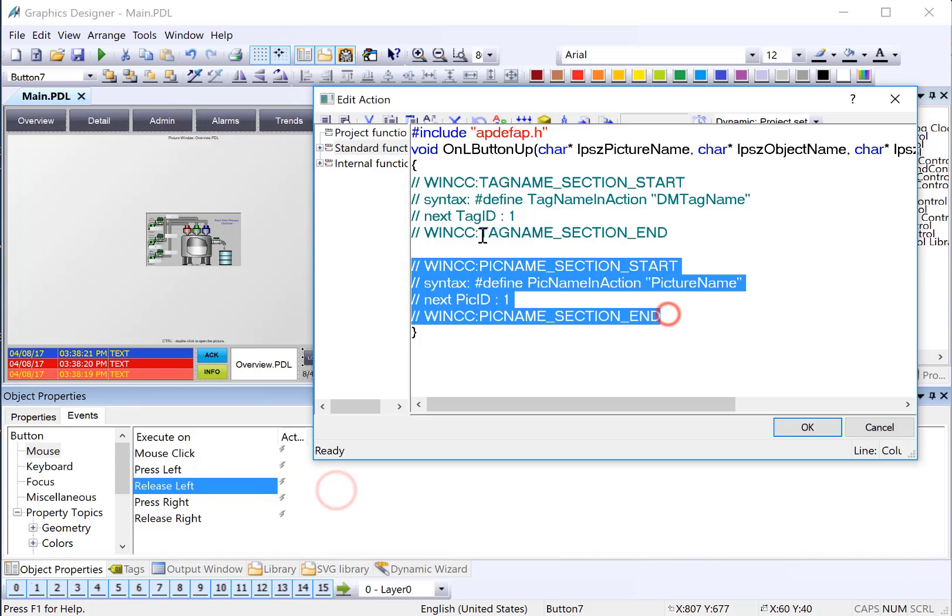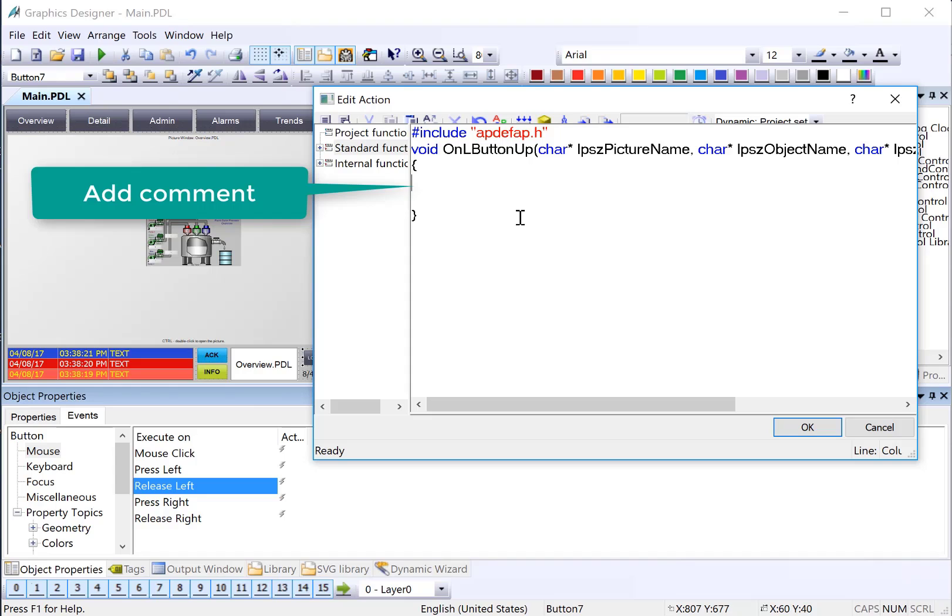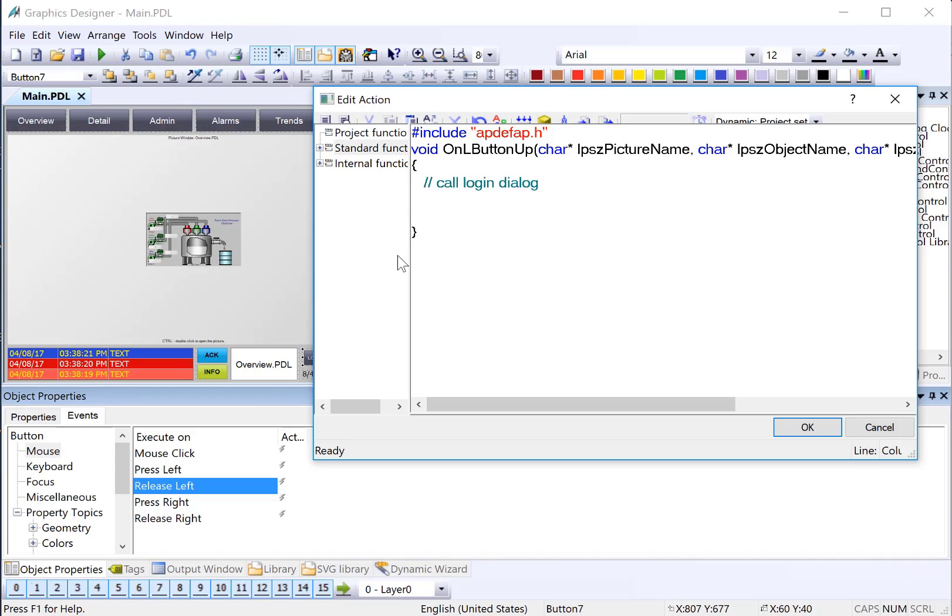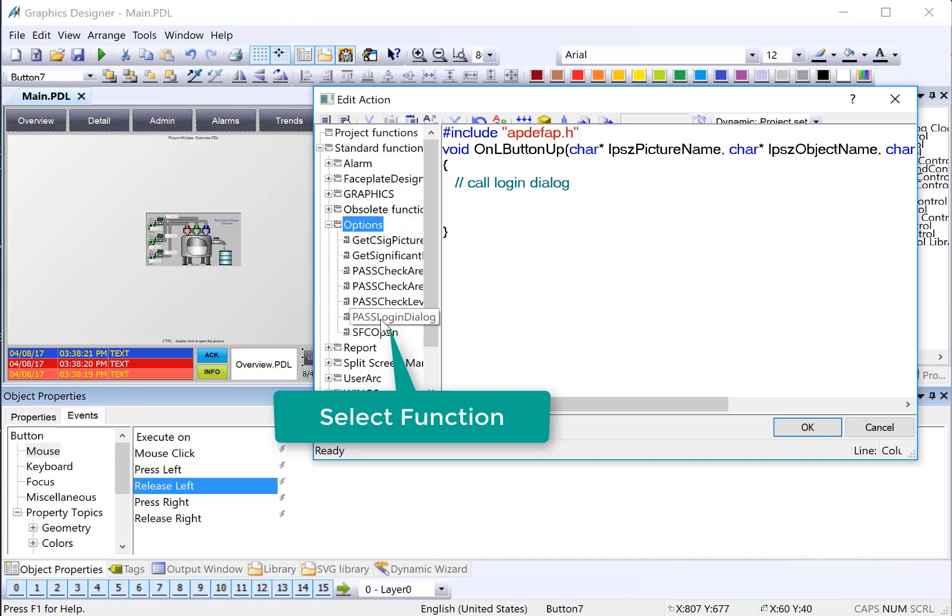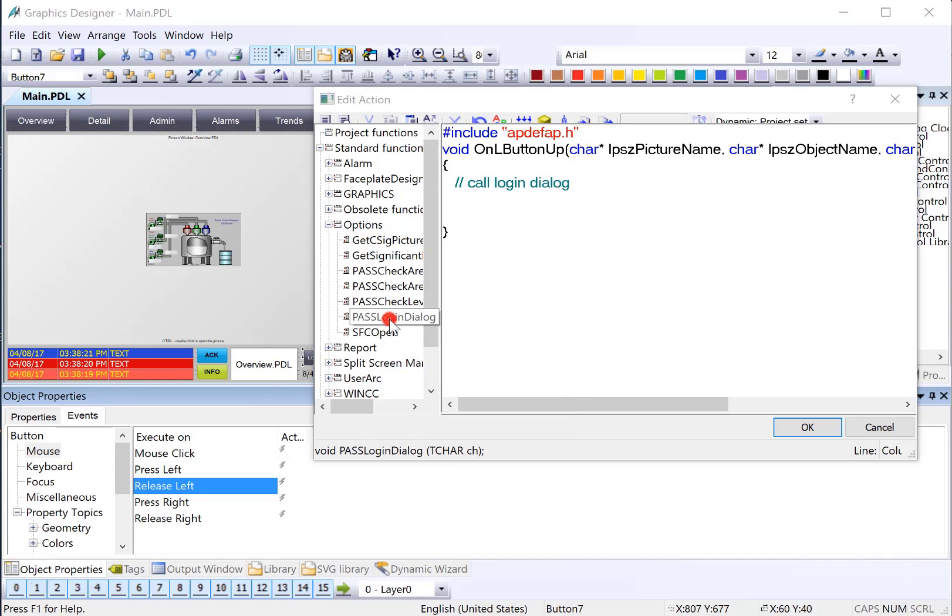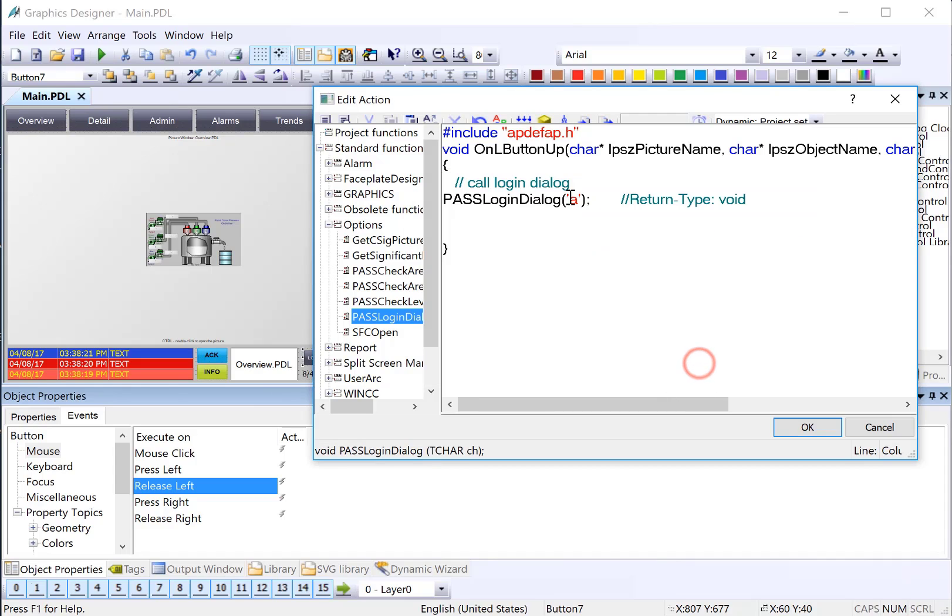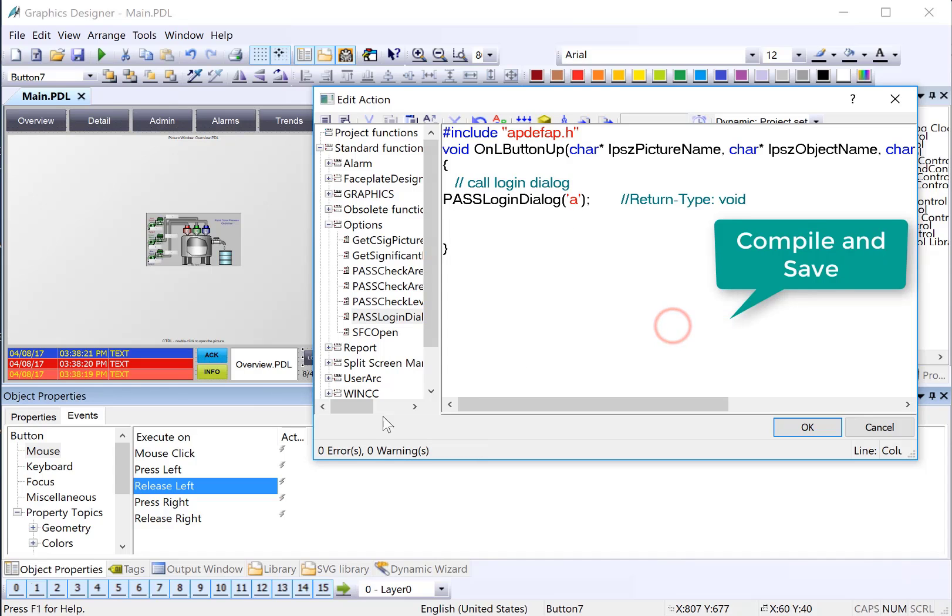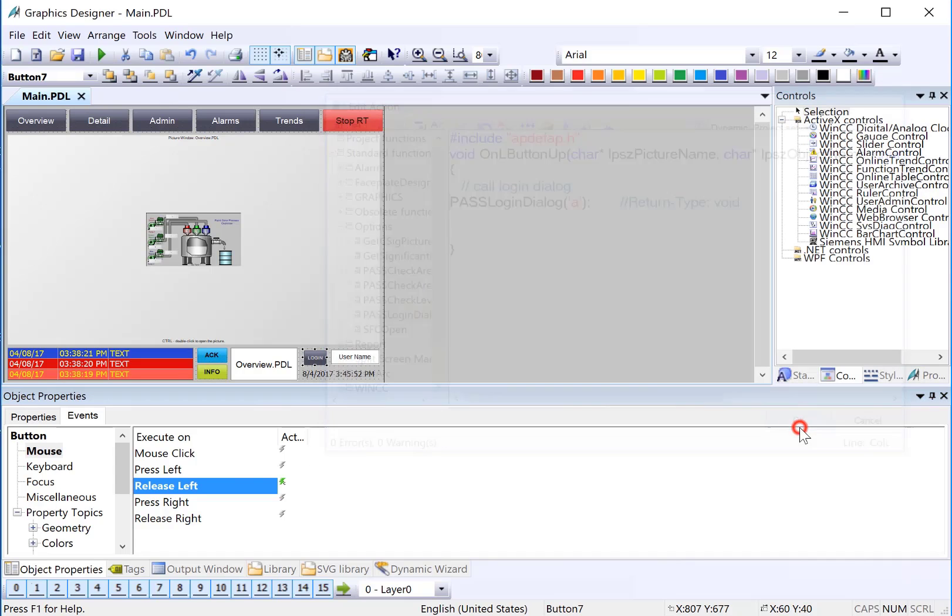In the C action dialog, we're going to delete the standard comments and add our own, call login dialog. And under standard functions, options, we will look for the PASSLoginDialog and just double-click. It's going to ask us for a single character and we are just going to enter A with single quotes on either side. Then we'll right-click, compile, check our errors and warnings, and click OK. You'll see that a C action has been added to our login button. Then we're just going to click save.